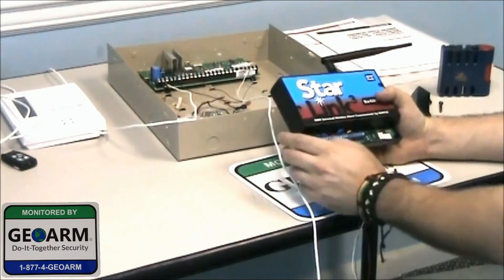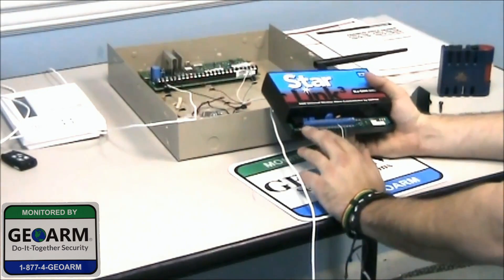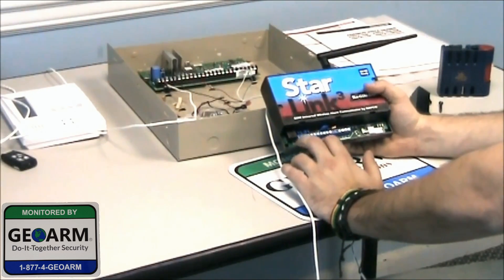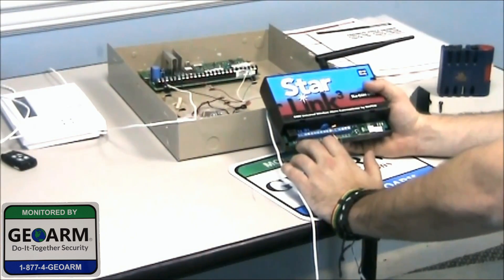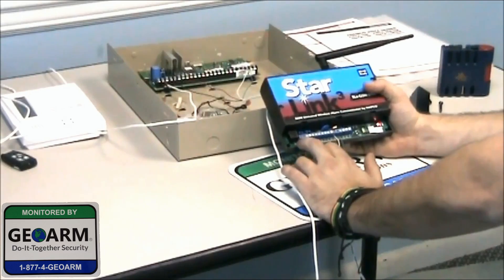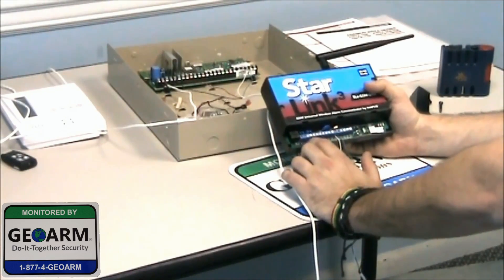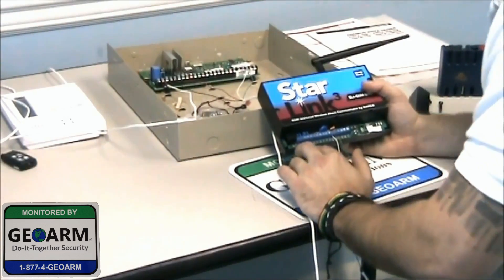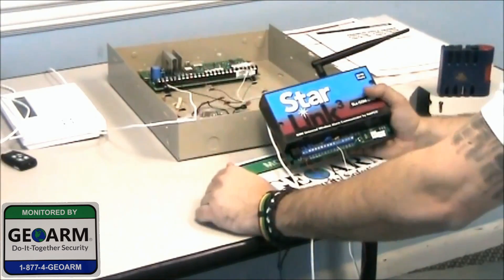But the wiring goes like this. Power plus and power minus are the first two terminals. We're going to go red, we usually use for positive. So we'll go red to power plus and then black to power minus. You're going to wire those into terminals 4 and 5 on the panel. Black is going to go to 4.